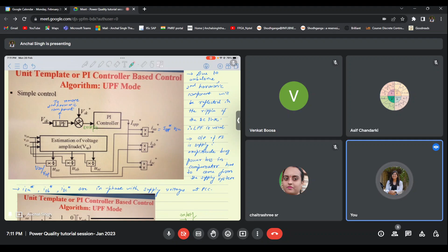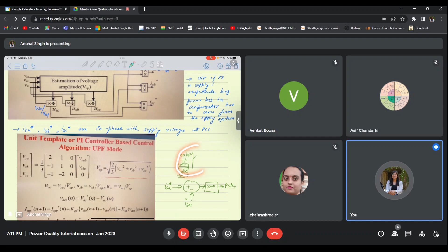So depending on the DC link voltage, whenever the compensator is operating, the DC link voltage will change. Whenever the DC link voltage changes, these references change, and when these references change, the gating pulses to the switches change. Then switches will operate differently depending on the reduction, and it will operate until this error becomes zero. And the moment this error becomes zero, this compensator will stop operating.